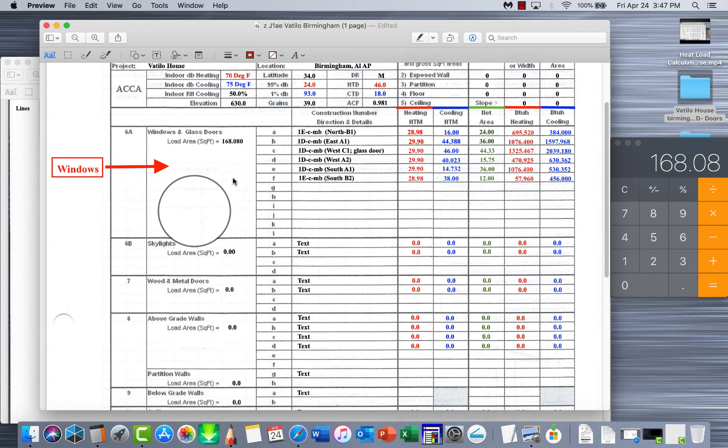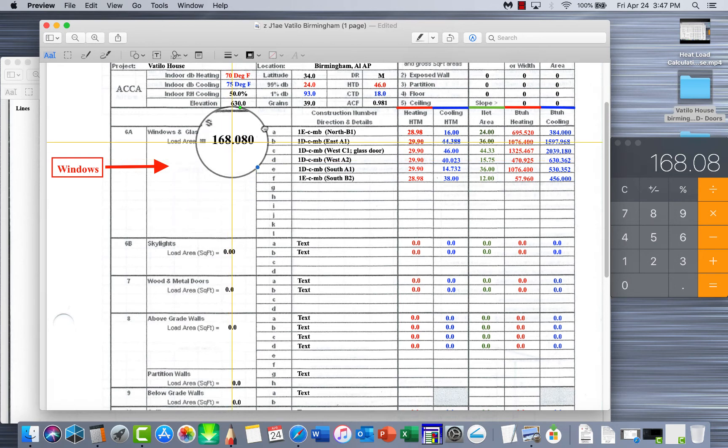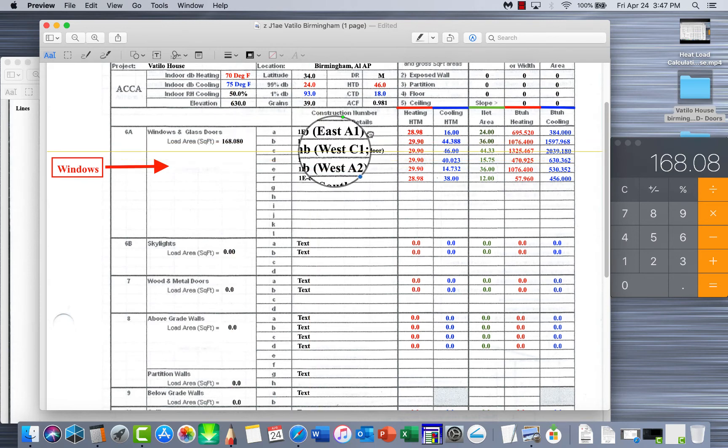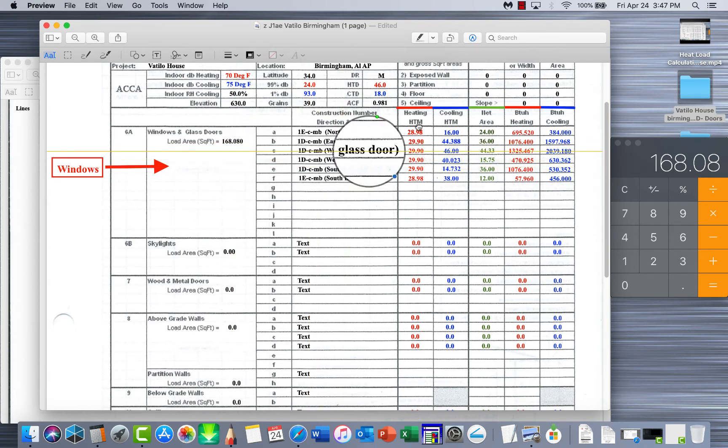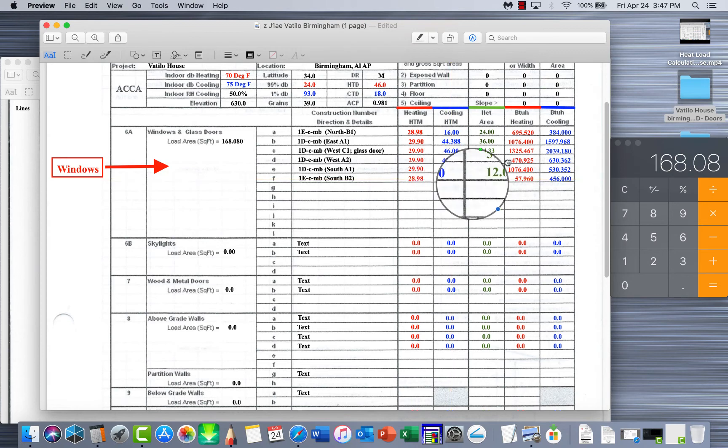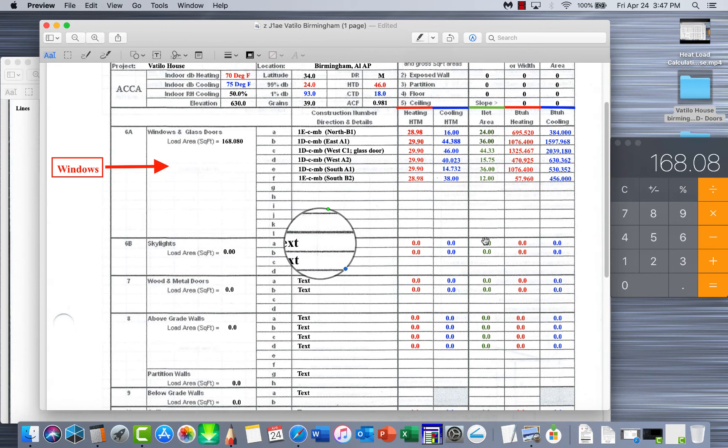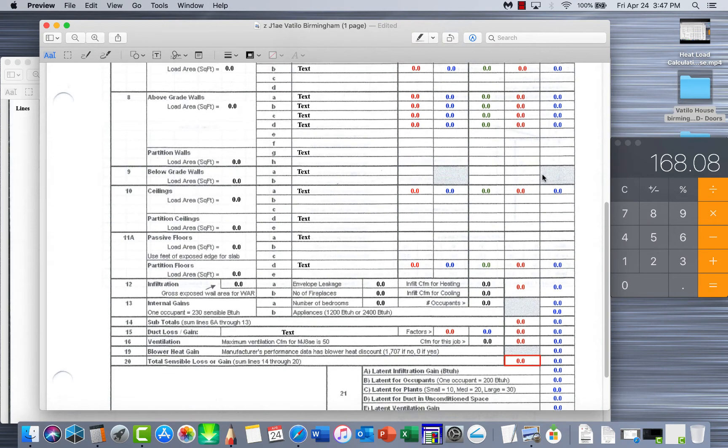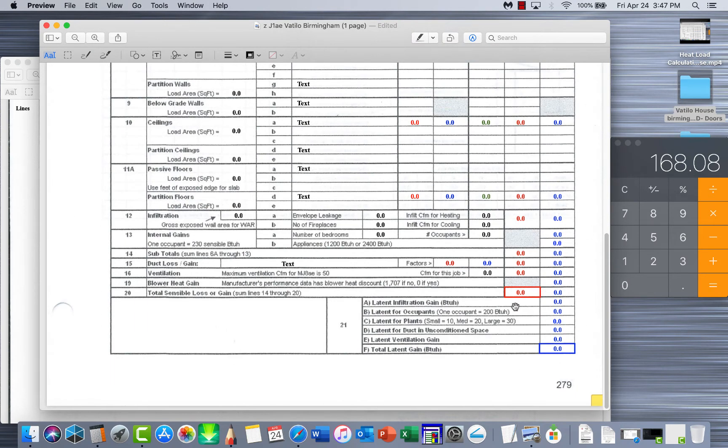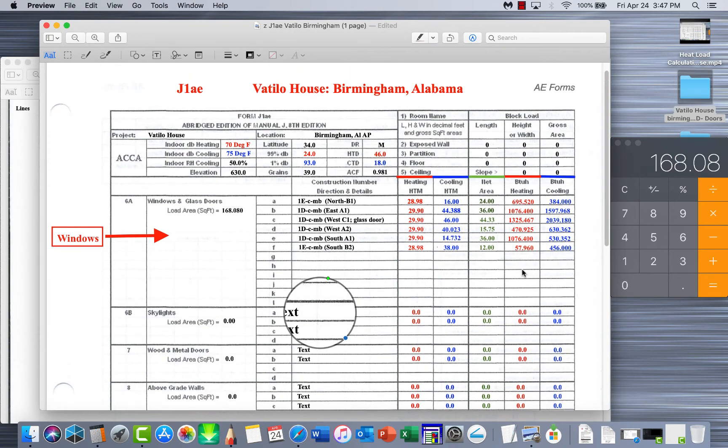If you've done all that and you've watched all these videos, you should successfully be able to do a complete heat load calculation, Manual J residential, on your fenestration, your glass, your windows. Make sure this is complete. Make sure all your denominations in here are complete. Make sure you get your correct HTM and cooling HTM, your net area, and then finally you get all your BTUs. Now what we'll do with all these final BTUs once we get down here to the bottom, this will be where we add all that up and get the final BTU requirement that you'd have to have for a piece of HVAC equipment to size a unit correctly.